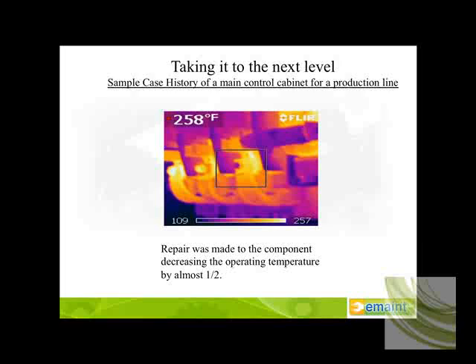One of the things I wanted to point out here is that even with electrical distribution in particular, and even with vibration analysis, when you find the main problem that you're initially reporting on within your process and your program—see my little arrow here—you notice that this leg now, the A phase, actually appears warmer than the B and C phase. The reality of the situation is that the repair was effected, and the next weakest link in this system is now exhibiting itself as a potential problem.